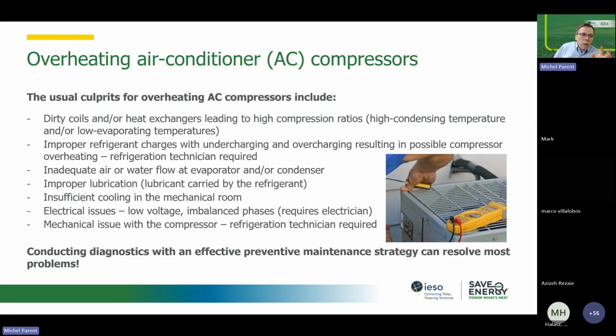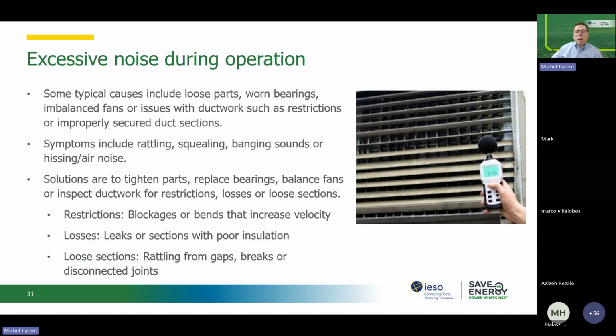It's usually not something that you would put in a PM program to check the voltage. It's only when you see that there are systematic failures of motors within your building, and you cannot relate them to any specific cause. It's a systemic cause, which usually comes from your electrical supply.